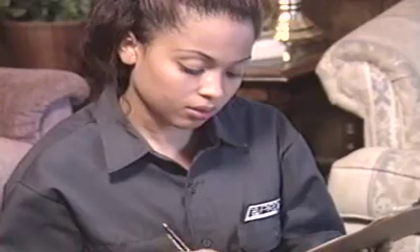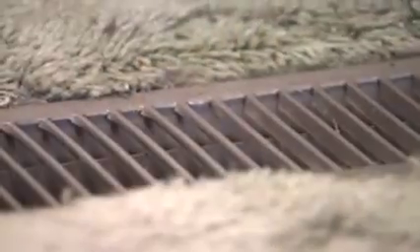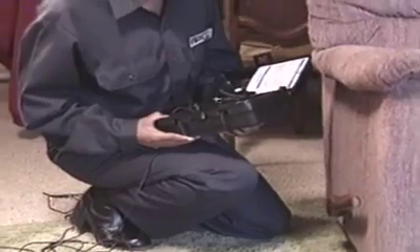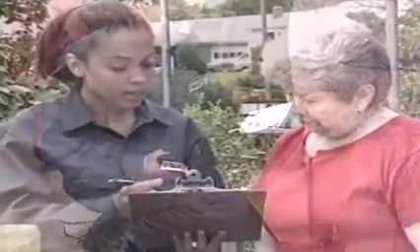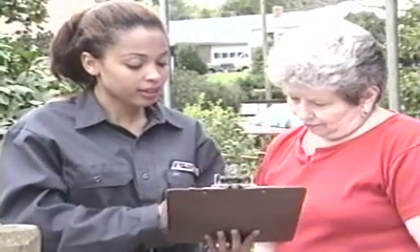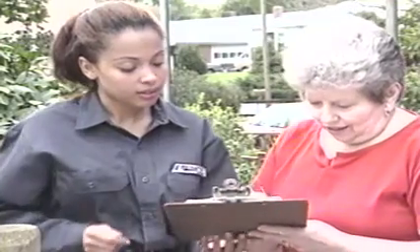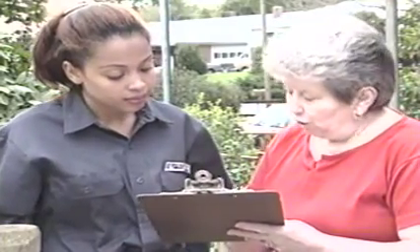Next, determine the wet bulb and dry bulb readings of the indoor air. Record them on the service invoice. Next, measure the actual supply air temperature. It falls in line with the calculator's requirements for the load conditions the system is dealing with. Complete the service call by explaining the charges on the invoice, making sure the paperwork is complete, and answering any questions.